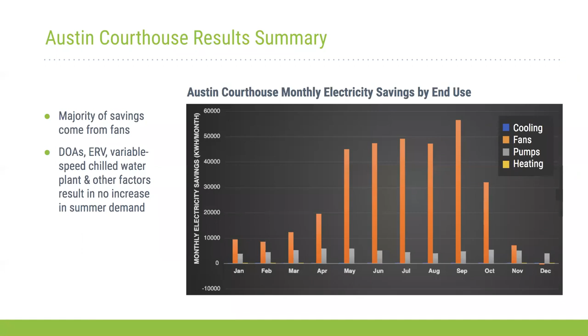This was very impressive. Allison had previously mentioned the GEB project we're doing, and this feature of the software actually feeds into one of our performance objectives for our next project evaluating this technology. We ran a two one-sided t-test and found 98.5% accuracy for Austin Courthouse and 97.5% accuracy for Dallas Terminal Annex. This compares the measured peak demand of the day against what the product predicts in the morning of that day, and we found high accuracies at all buildings.